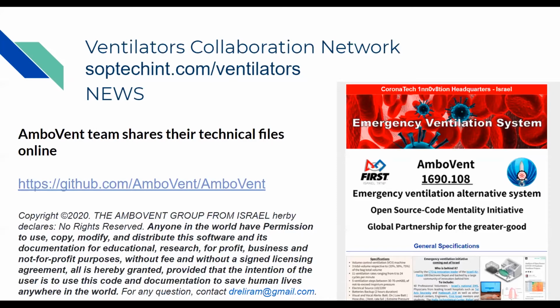Okay, no worries. Anyways, it was designed to be really simple. The design is made so that the BVM is open to reach in case of malfunctions, and you can calibrate the machine to different BVMs, because we know there are a lot of different models being used in different hospitals in Israel. So we try to make it as modular as possible.